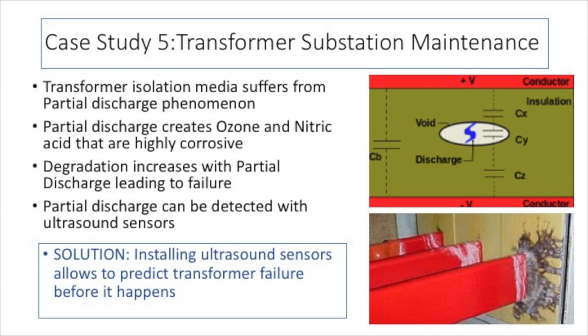There are two ways to measure the partial discharge phenomenon. One is measuring the UHF, ultra-high frequency emissions. The other one is ultrasound. We found the ultrasound to be much more effective, with a better signal-to-noise ratio. There is no external interference that could affect the readings, and there is a lot of research on that particular field, and still a lot to be done in partial discharge research and substation maintenance with utilities.